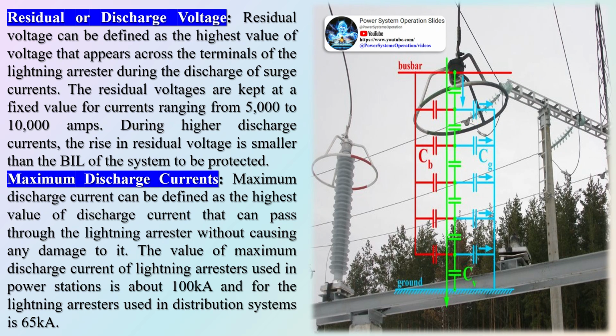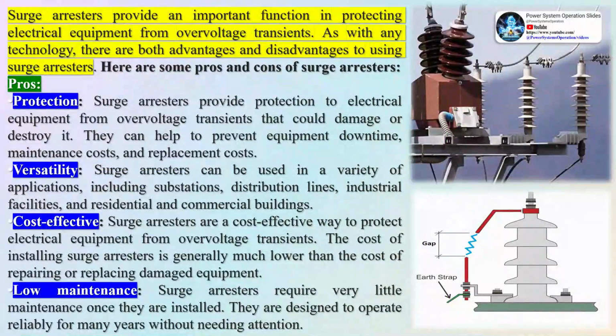Main differences between surge arrestor and lightning arrestor. A surge arrestor is installed inside the panel board, while a lightning arrestor is installed outside. A surge arrestor protects the installation from inside, while a lightning arrestor protects the equipment from outside. A surge arrestor protects the system from lightning, switching, electrical faults and other transient voltages and surges, while lightning arrestors are mainly used for lightning strikes and associated surges.